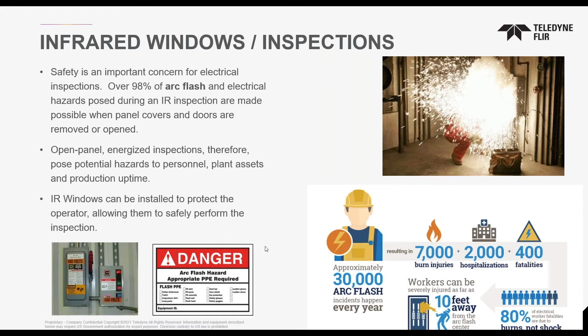98% of arc flash and electrical hazards posed during an IR inspection are made possible when the panel covers and doors are removed or opened. So if you can always keep that panel door closed, you eliminate about 98% of arc flash incidents. Once that panel is open, there's a lot more danger to yourself, the people around you, and your facility. With an IR window, it allows you to do these inspections while keeping that cabinet door closed.